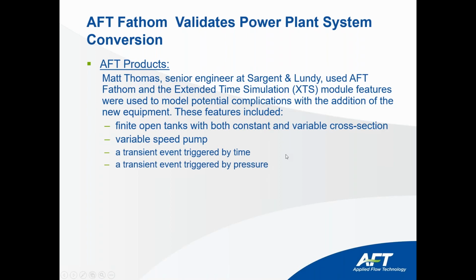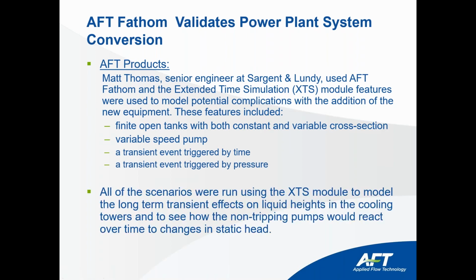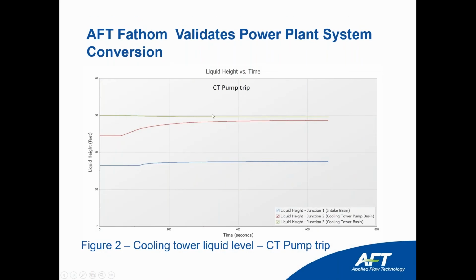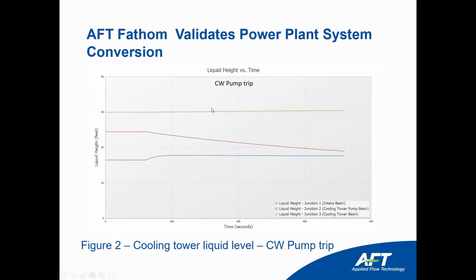So as we saw, engineers used AFT Fathom and the XTS module featuring finite open tanks with both constant and variable cross sections, variable speed pumps, a transient event triggered by time, and a transient event triggered by pressure. All the scenarios were run using the XTS module to model the long-term transient effects of liquid heights in the cooling tower to see how the non-tripping pumps would react over time to changes in static head.